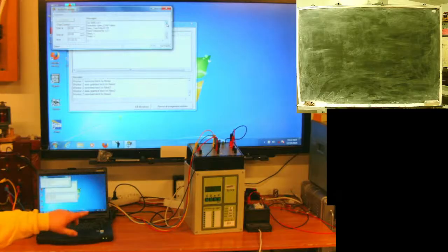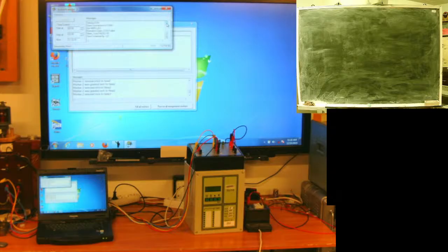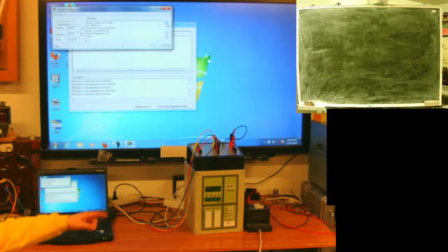Two-level integration. A device like this previous model was able to read data from 4 fault locators. It was a two-stage system. Wait, this disassembled one, here it is. One disassembled, 4 of them, up to 8, but I only saw a manufactured version of 4. 4 fault locators, in case they detect a fault on the line, calculate fault distance and throw data to the central unit.